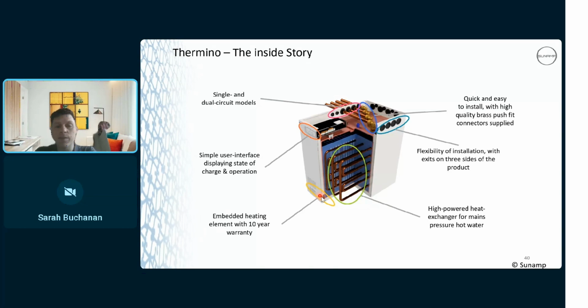You've got your element, which is fixed, embedded in the bottom here, with a 10-year warranty, and that's your heat exchanger. So essentially, what is a heat exchanger? We've got a coil of pipe with aluminium convector fins. Just think of it almost like a car radiator that's sitting in this plastic cell here, and it's enveloped by this PCM. So once the PCM's up to temperature, you run water through there, and all it's doing is catching the heat. And that's essentially what's creating this phase change chain reaction. So it's the movement of the cold water which is causing the chain reaction. As soon as you stop the water, the chain reaction stops.